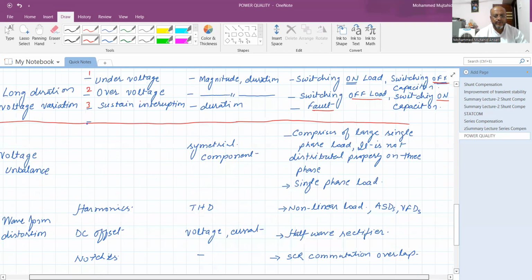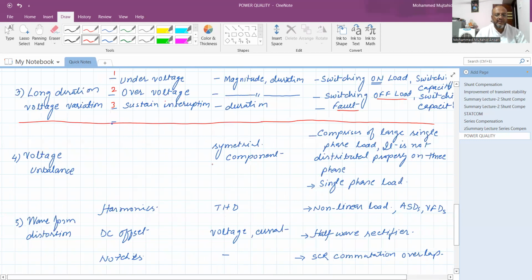Next is voltage unbalance. The voltage unbalance is measured with the symmetrical components, and it is due to a load comprising a large number of single phase loads, that is the lighting load, and many times the load is not properly distributed over the three phases, and it will lead to unbalanced voltage in the three-phase system. Or it may be only single phase loads, like a large number of single phase motors, which will definitely make the system unbalanced. So this is the next.